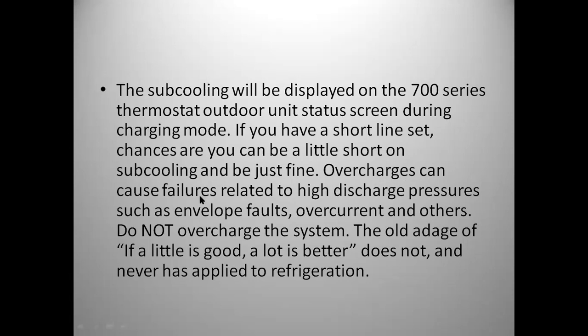So if you have overcharges, it will give you high discharge pressure faults. It'll give you envelope protection faults. Overcurrent's a big one. Overcurrent's going to go along with static pressure and overcharge, and there's a few other ones you'll get as well. Whatever you do, do not overcharge the system. If a little's good, a lot's better, we'll buy you a new compressor with these. You can usually tell with the sound, because these are distinctly different sounding, but they're relatively quiet. If you overcharge one, they get violent. They do not like that, and you'll hear it.